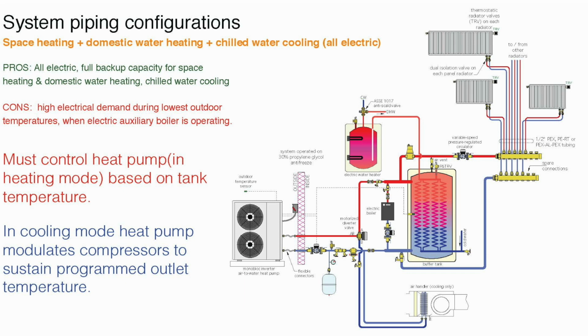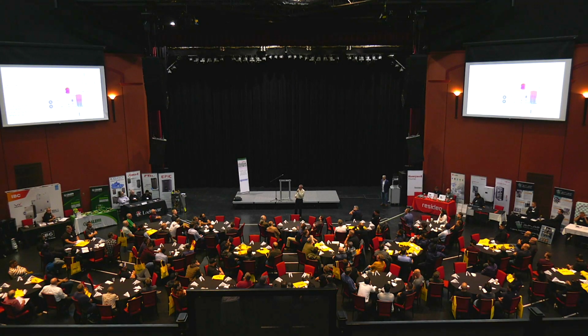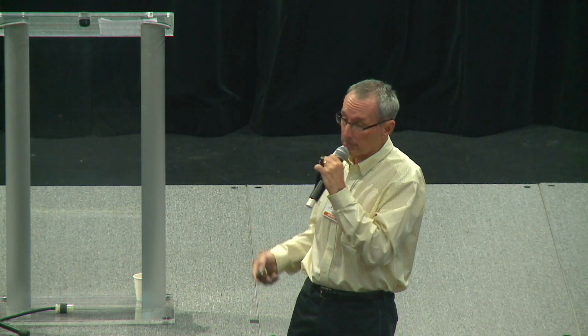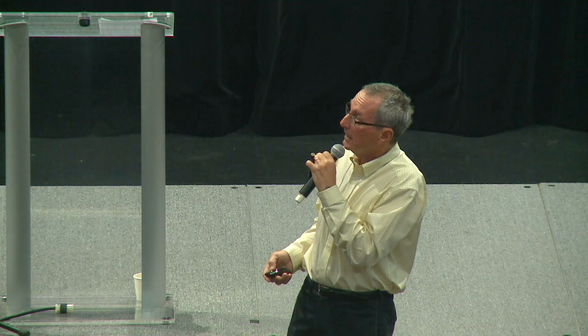And I'm showing a backup for domestic hot water. That would be necessary if you're using outdoor reset control on the water temperature in the buffer tank. And our simulations have shown that is better than maintaining the buffer tank hot enough all the time to completely heat the domestic hot water. That was one of the big questions I had. Are we better to use outdoor reset and have more direct electric resistance heating of domestic water? Or are we better to maintain the tank at a higher temperature all the time using the heat pump and have a slightly lower COP from the heat pump? Well, the outdoor reset control wins, okay?